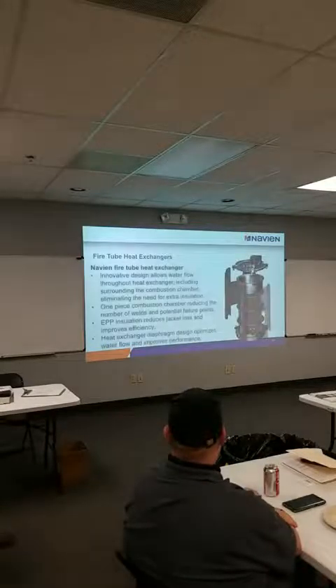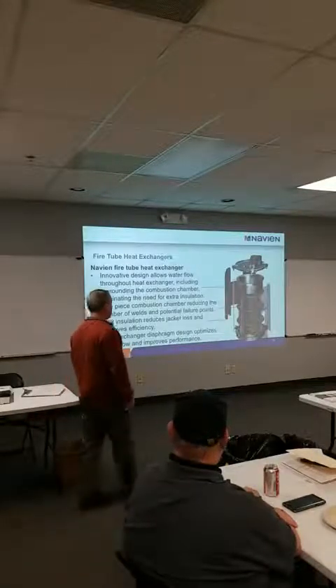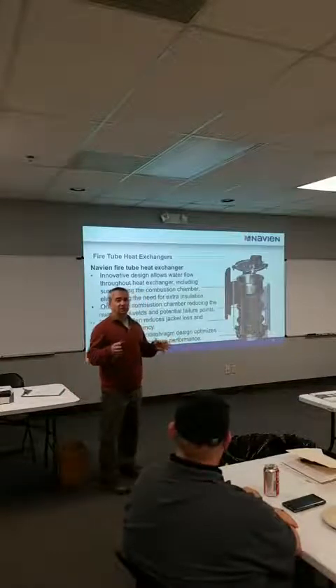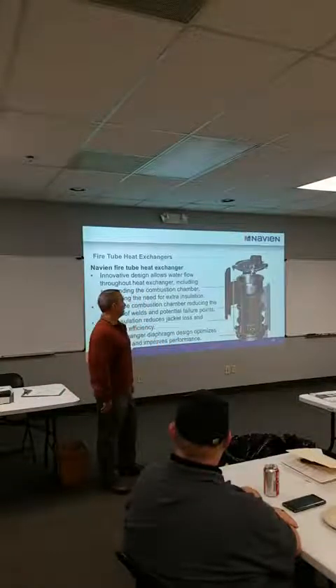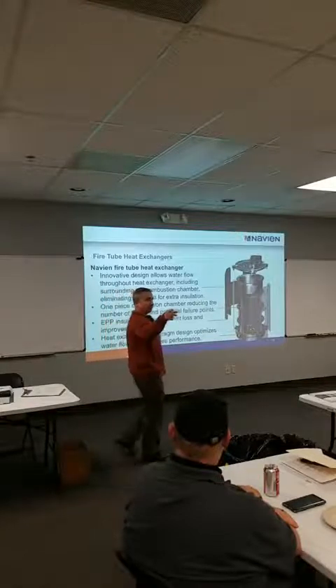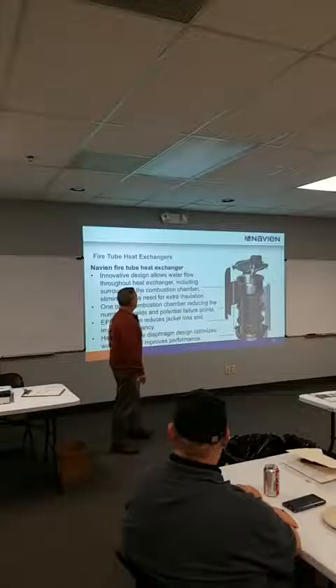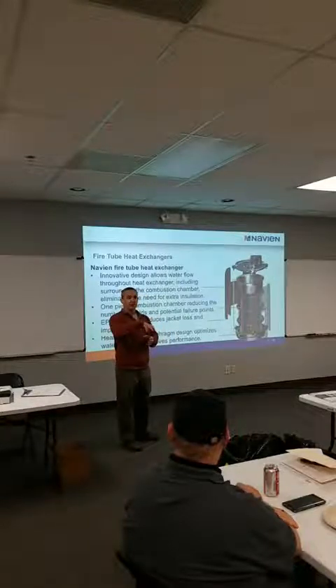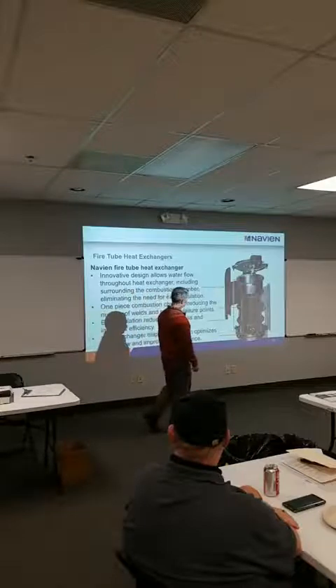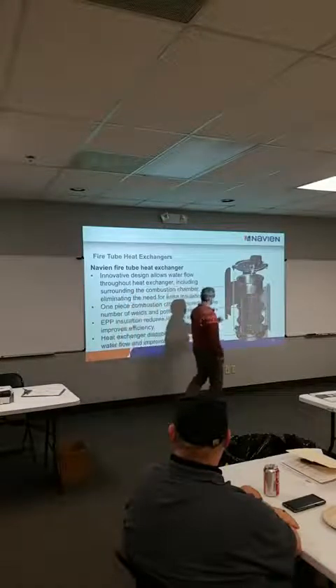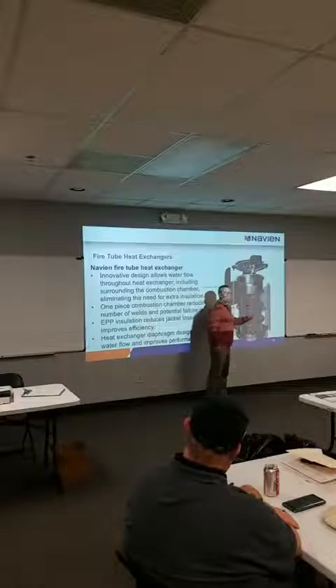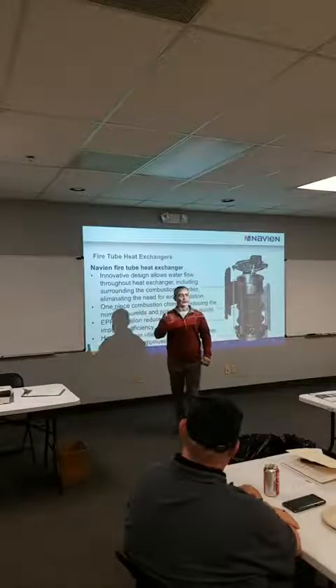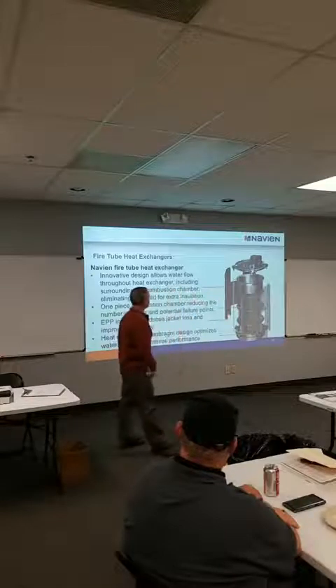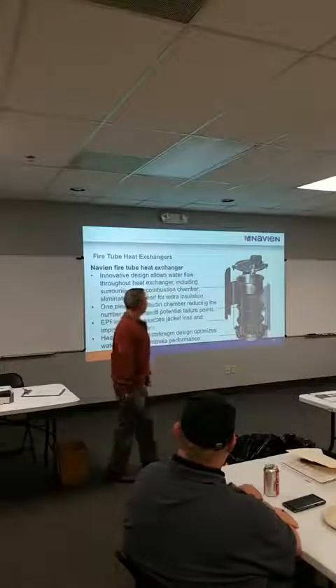So this is our fire tube heat exchanger. Everybody's fire tube heat exchanger kind of looks the same if you're just looking at it from the outside. They did make a lot of changes. I mean, I sold for NTI and I've seen triangles. Ours is a lockdown 4-bolt assembly on top, and it swivels. It's like a turn lock, and then you can tighten down those bolts. All of our inner vanes are nippled on the outside, so as water's going through there, it agitates and helps keep that heat exchanger clean. Turbulent, increases efficiency. Yep.